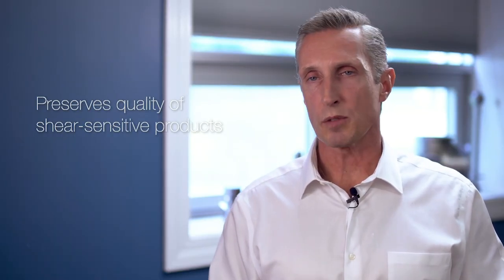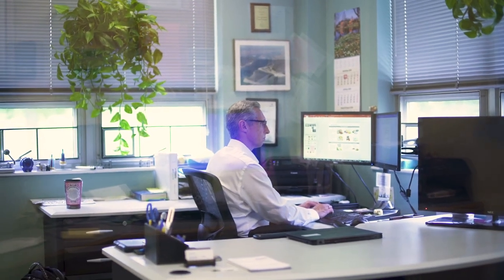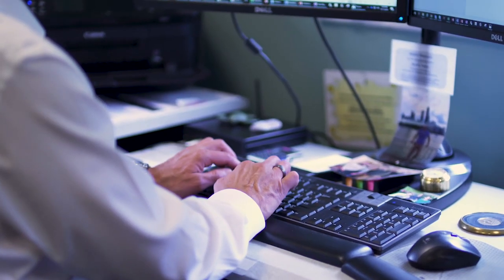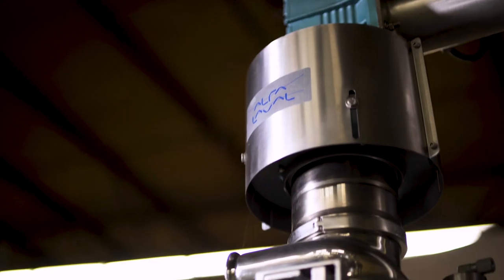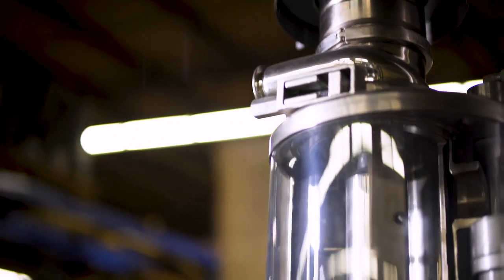It's extremely flexible. Gasketed plate and frame heat exchangers or tubular heat exchangers have no moving parts, so I'll refer to them as static heat exchangers. We can design them — and Alfa Laval does an amazing job optimizing them — but at some point they reach their limitation. You get to the point where you physically need something mechanically removing that fouling layer, and that's where the scrape surface heat exchanger comes in.